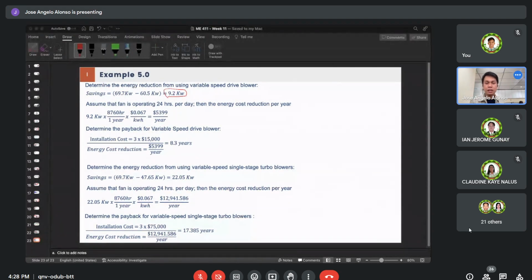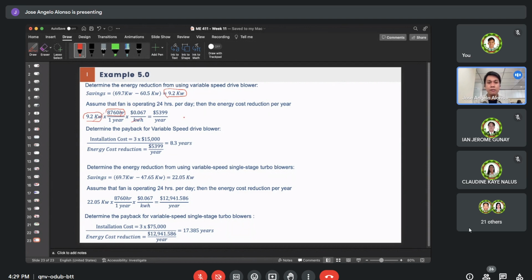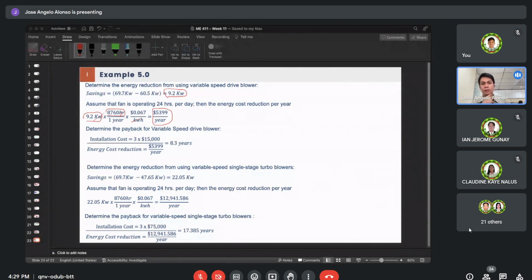Let's convert that to how much we save per year, assuming the fan operates 24 hours per day. So that's 9.2 kilowatts multiplied by how many hours per year — since the fan runs continuously 24 hours a day, that's 8,760 hours per year. Multiply that by the cost of electricity, which is $0.067 per kilowatt-hour. After canceling units, this gives us savings per year of $5,400. That's not bad either, right? That's a fairly large savings — that's now in terms of dollars, not kilowatts. So when installing the VFD, we already have savings of $5,400 per year.